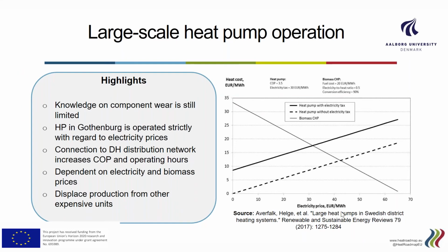The connection to the district heating network is also important. A study on the potential of installing heat pumps in Copenhagen showed that if heat pumps are connected to the distribution network, they can have a higher COP and more operating hours than if connected to the transmission grid, where they have lower COPs and fewer operating hours. However, the downside of connecting to the distribution grid is that it can only supply a limited area, while a connection to the transmission network can supply a larger area. Of course, heat pumps are dependent on electricity, biomass, and fossil fuel prices.